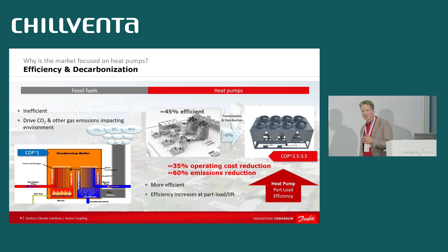But even with that baseline, you're still talking about a 35% operating cost reduction, and this is highly dependent, and a 60% emissions reduction for replacing that condensing boiler with an air-to-water heat pump, using, and Kim touched on this as well, a grid that is 100% supplied by fossil fuel sources, so a combined cycle natural gas plant. If you do the math on that, you're still significantly decarbonizing because of that baseline you're comparing to, and significantly less efficient with converting energy.